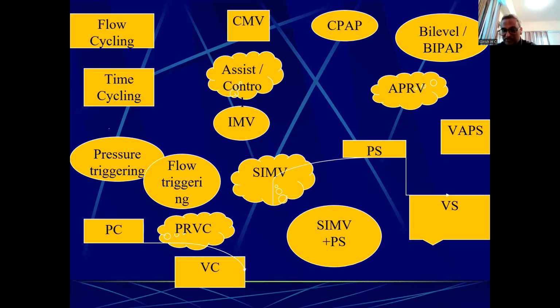That is very, very important because a lot of these modes, for example volume support, somebody may call volume guarantee, but volume support and volume guarantee are essentially the same. Or mandatory minute ventilation may be the same as volume guarantee. So it is important to go to their manual and read and see that that's what they mean, right?